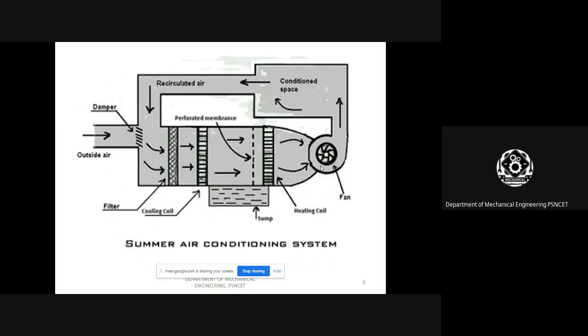Now we see the summer air conditioning system here. The outside air is passed through the circuit, purified and humidified to the conditioned space. You see the parts available in this air conditioning system: first one is the filter, second one is the cooling coil and the perforated membrane, then again the heating coil. It is pumped through this fan to the conditioned space and recirculated, the air inside the conditioning system.